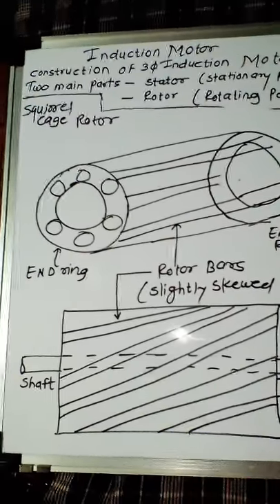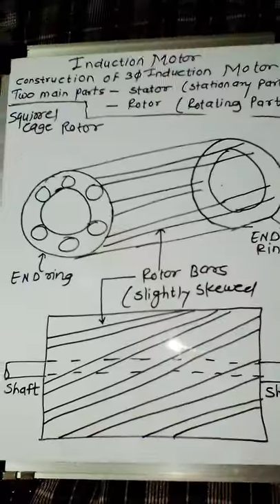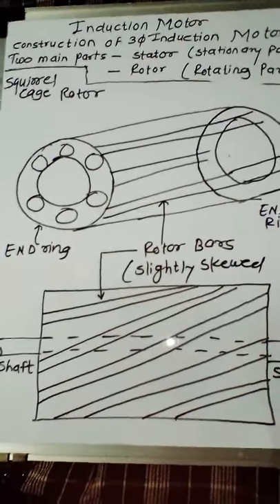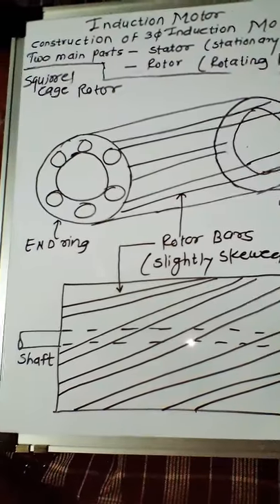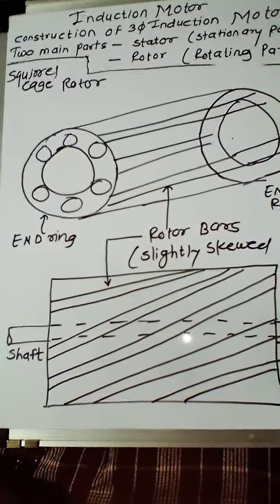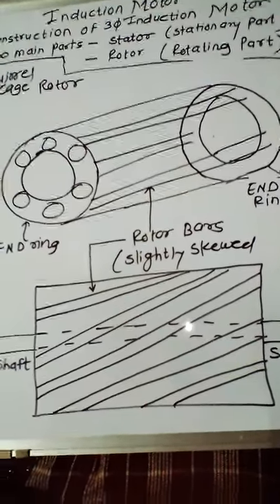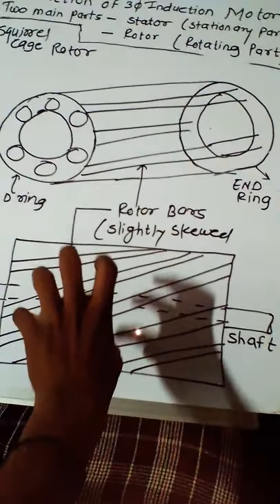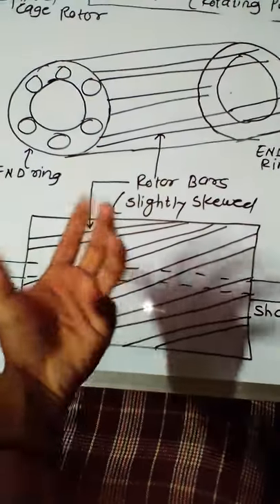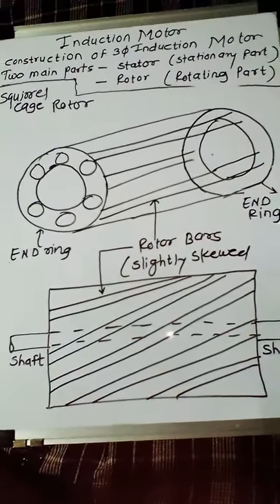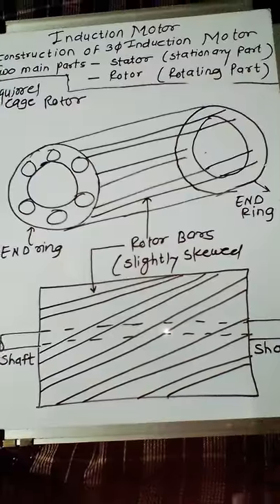This type of rotor is widely used in induction motors. The slight skew of the rotor bars also helps the three-phase induction motor run quietly without producing any magnetic hum — this is another advantage of the squirrel cage rotor. The motor starts without producing any noise, and the magnetic interlocking tendency of rotor bars with respect to the stator bars is reduced because of the slightly skewed bars placed in the rotor slots.